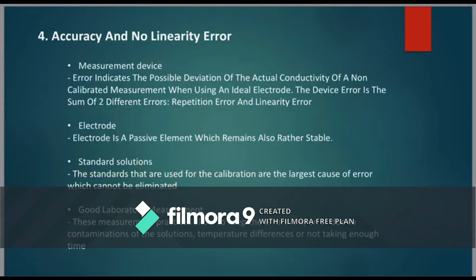Accuracy and non-linearity error consists of 4 types. The first is the measurement device, second is the electrode, the third is the standard solution, and at the end is good laboratory measurement. For the measurement device, the error indicates the possible deviation of the actual conductivity of a non-calibrated measurement when using an ideal electrode. The device error is the sum of two differences, which are repetition error and linearity error.